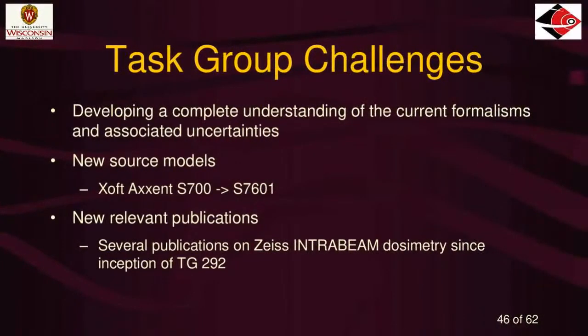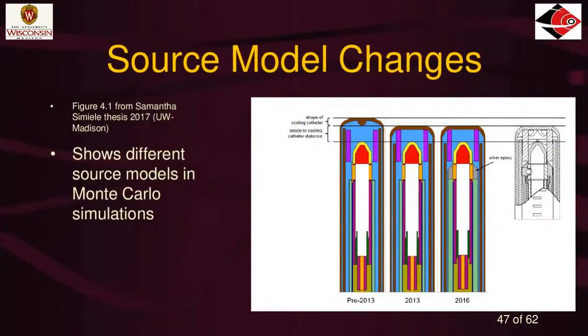The challenges facing our task group include developing a complete understanding of the formalisms from the manufacturers, dealing with new source models and new publications that have come out in the last five years since we started. For example, three Monte Carlo models of the Xoft Axxent source over the last seven years show differences — small tweaks to models that change dosimetry parameters over time. That's a challenge when dosimetry parameters change.